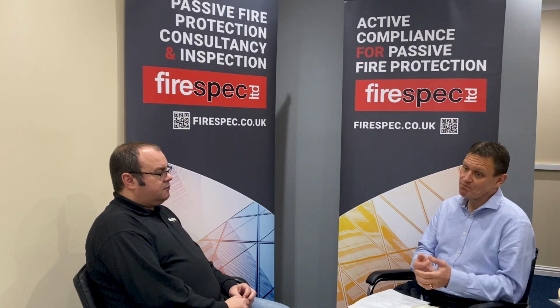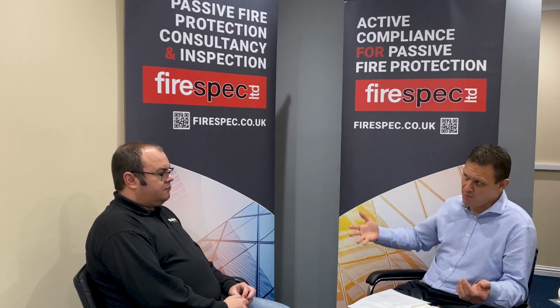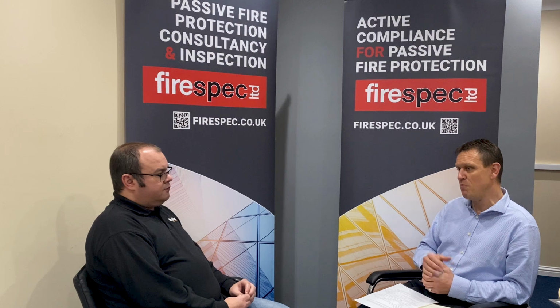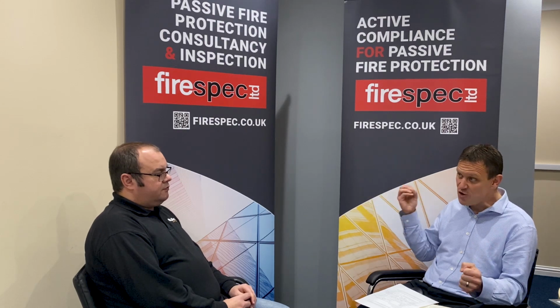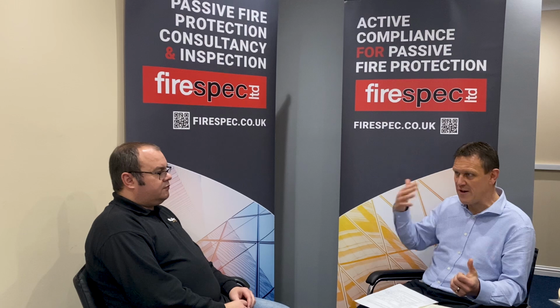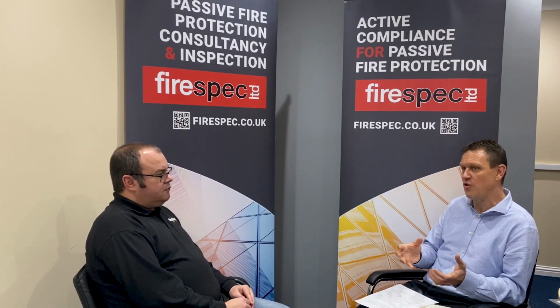We've got a fire strategy, then you find that you're trying to achieve EI ratings, integrity and insulation ratings, of 60 and above. They can be particularly difficult to achieve, anything 60 and above, even 60 on certain types of details with certain types of products passing through. And it's the misunderstanding, or the lack of understanding, of how to achieve that and how important that insulation rating is. There's a great lack of understanding on that insulation rating. That comes from specifiers right down. We find specifiers don't appreciate what the insulation rating is. I think the industry hasn't historically understood what this insulation is and why.